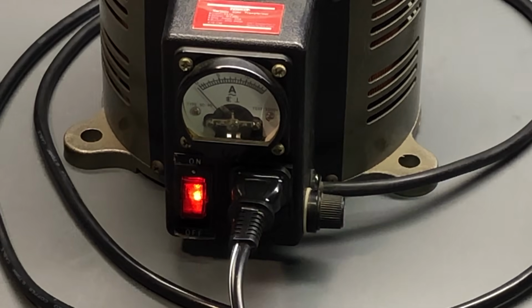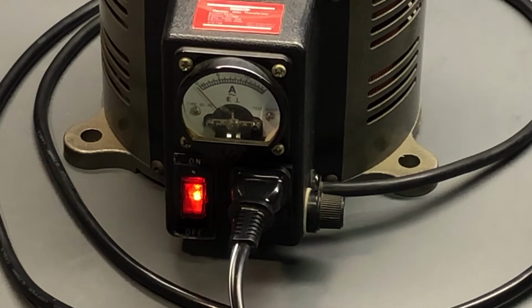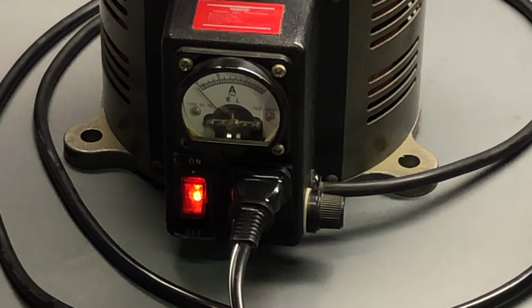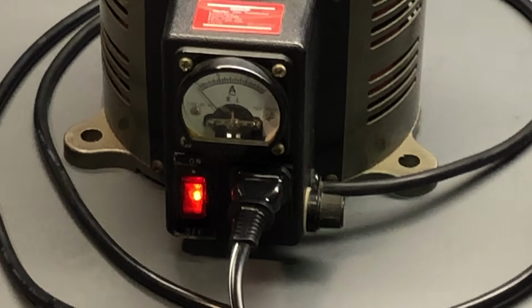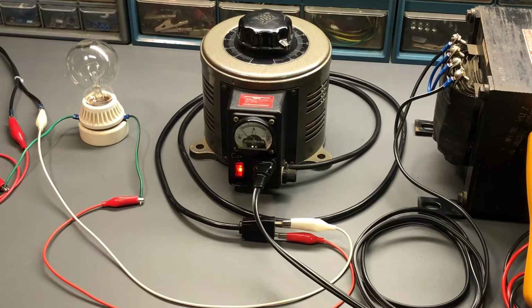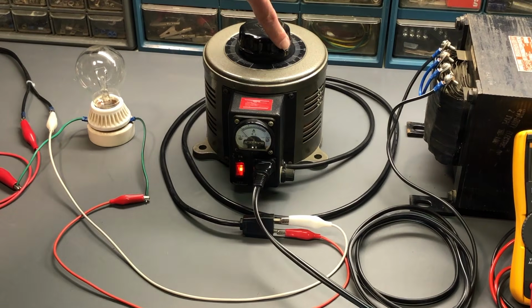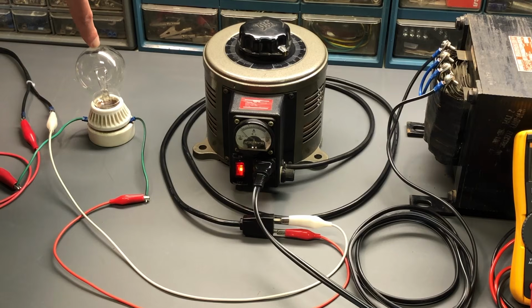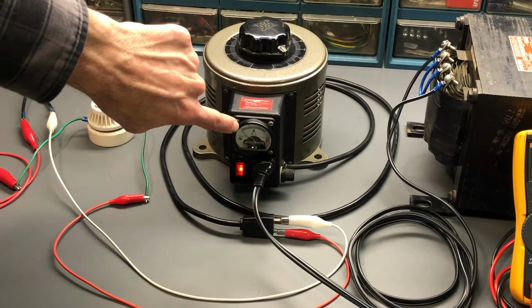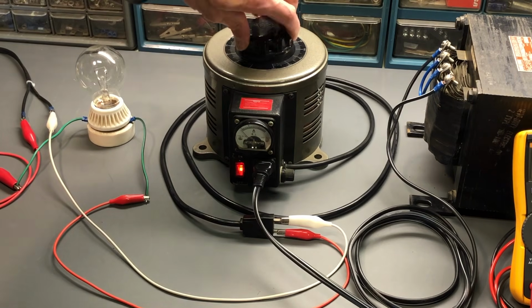If I remove the short, which I will do now. Take that off. Okay, so the secondary of the transformer has no connection to it. All right, so there's no load connected right now. And if I increase this up, you can see now, back the camera out, you can see over here, this is at 120 volts. We have no current flow, so the lamp remained off. This never jumped up.